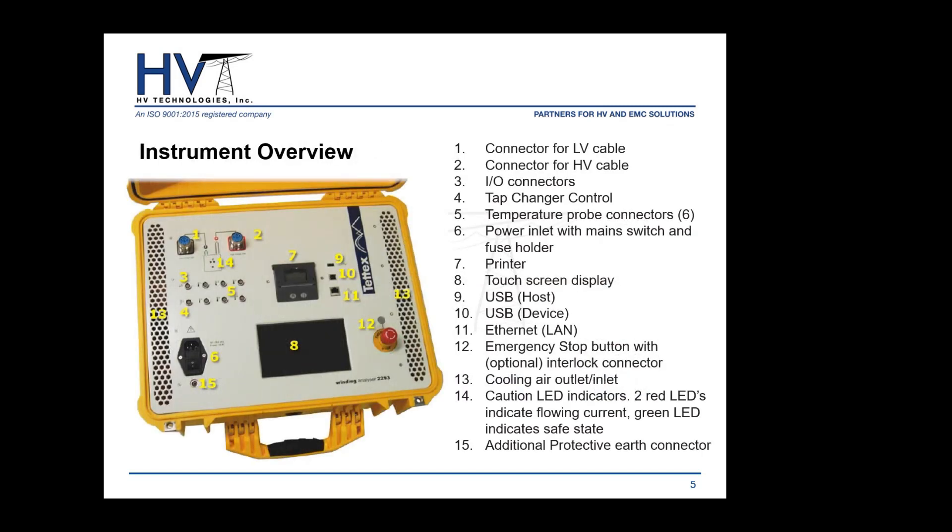Getting into the instrument itself — it's very clean and simple. The only button is the emergency stop. At the top left you have your connectors for your high and low voltage cables. The connectors are twist-lock: plug in, quarter turn, and they're secure. Just under the connections are LED indicators which turn green when the instrument is safe and red when it's supplying power to the device under test.